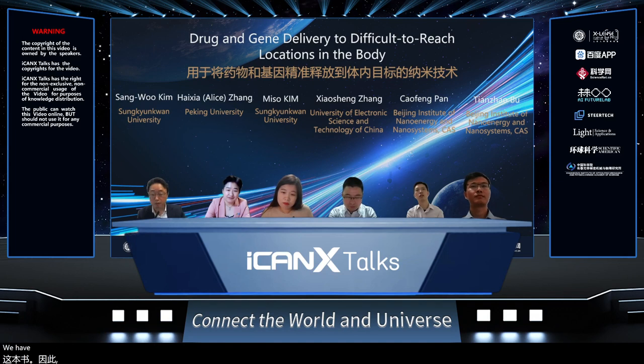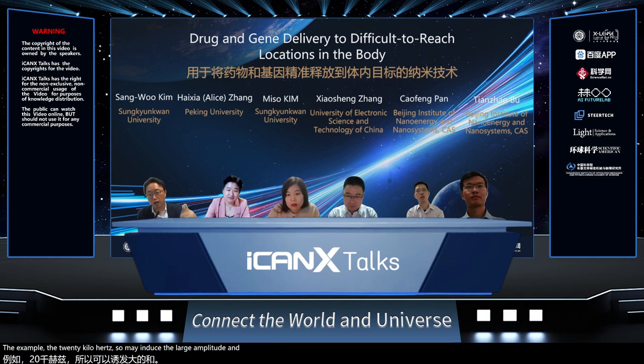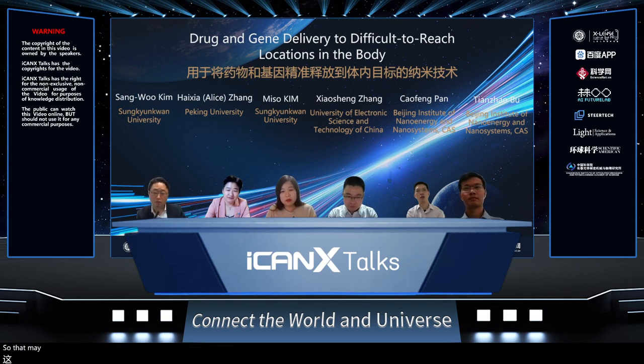We have to secure the ultrasound range for FDA permission, so for example less than 100 kilohertz. For example, 20 kilohertz may induce large amplitude and also cavitation inside the blood, which may increase body temperature.